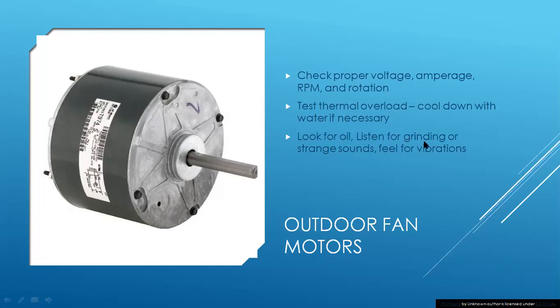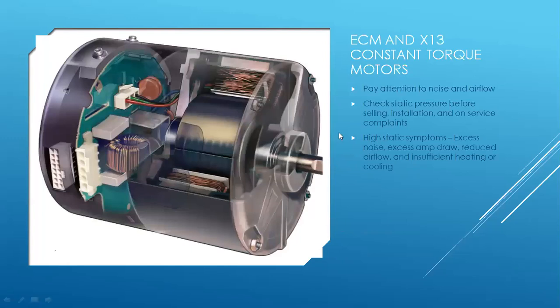Look for oil. Listen for grinding or strange sounds, and then feel for vibrations. What we're getting into more and more here is the ECMs and X13 constant torque motors. This is huge. In fact, that's all you get on furnaces now. So you've got to become very familiar with this. Pay attention to noise and airflow. If it sounds like a jet engine in there, if it sounds like it's struggling and there's an airflow issue, either on supply or your return, so if it sounds rough, get to the bottom of it pretty quickly.